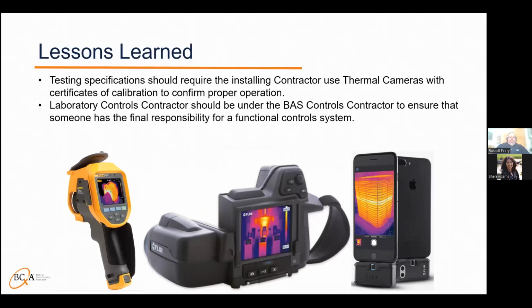Some lessons learned: testing specifications should require that the installing contractor use thermal cameras with certificates of calibration so that they can confirm proper operation. We've got a few examples of pictures on there. And then of course, we previously touched on it, the laboratory controls contractor should be under the BAS controls contractor to ensure that someone has that final responsibility for a functional control system and is coordinating an effort for a turnover of a functioning system.